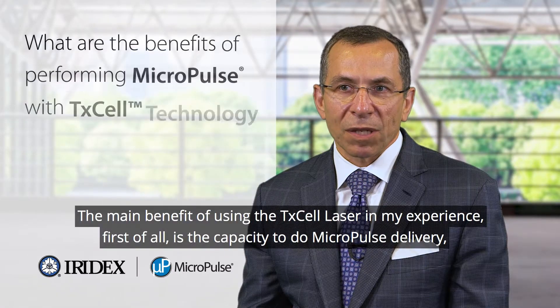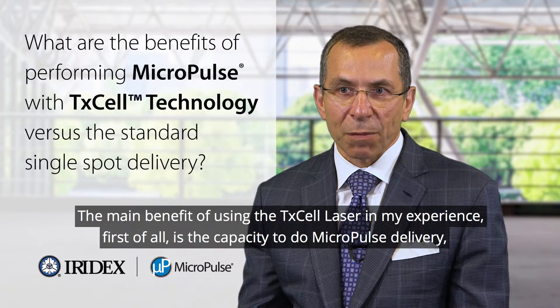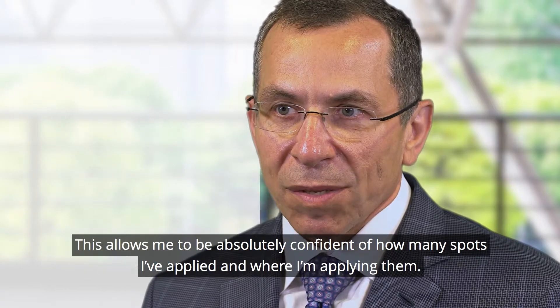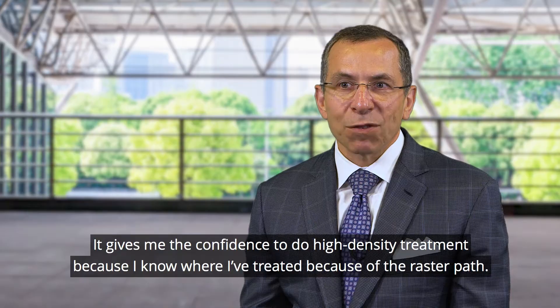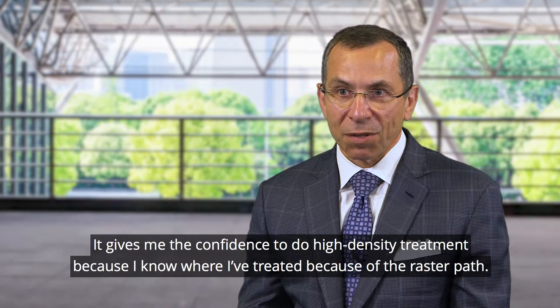The main benefit of using the TxCell laser in my experience is, first of all, the capacity to do Micropulse delivery, and secondly the raster delivery system. This allows me to be absolutely confident of how many spots I'm applying and where I'm applying them. It gives me the confidence to do high density treatment because I know where I've treated because of the raster pattern.